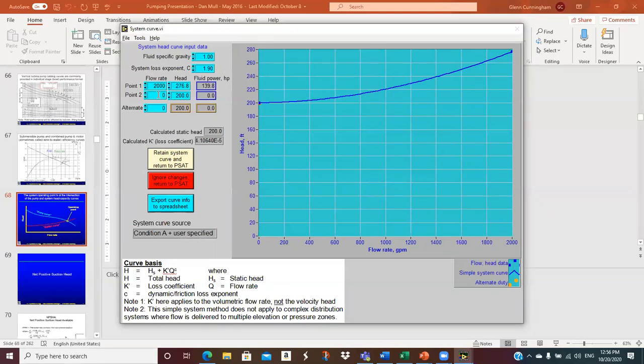Put in 0, 0. Then you just have to have one more operating point, and that's usually the point where you go up to the pump and it's operating. Well, that has to be on the system curve if it's operating on the system. And so you can take measurements on that operating pump and try to determine the pump head. We just saw how to calculate pump head, measure the flow, and you're good to go.